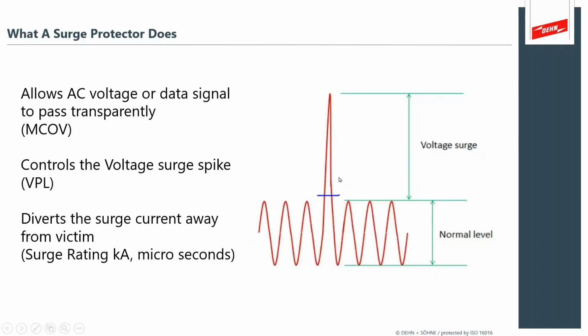So the most important things, lots of things are important. The key things to look for right away is, what's the operating voltage, the maximum continuous operating voltage of your circuit? If it's AC power, fine. If it's 4 to 20 milliamps, we know that's 24. Boom, we can just march down, talk about the voltage. Then it's the VPL. What does it really control that to? If it's a really sensitive 5-volt circuit, you want a really sensitive VPL.